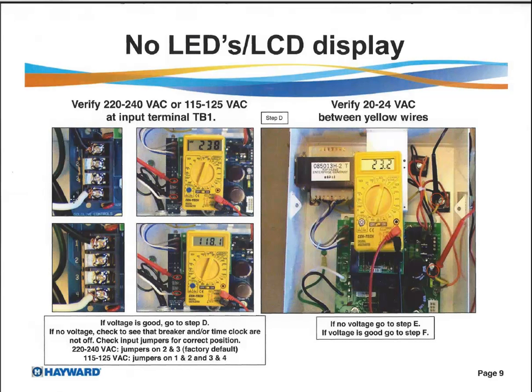This is a good picture. This should be a black and a black, or a black and a red. It should not be white. But anyway, you're checking for voltage, and you're checking for 230 or 240 volts between tab 1 and 4. Then again, if you're wired for 115 volts or 120 volts, however you want to say it, you tab it between 1 and 4, and there's your voltage. This white wire is correct to me, and most, though I don't know codes all over the United States, a white is a neutral. So they should have striped this black or red. The green is good, that's no problem.